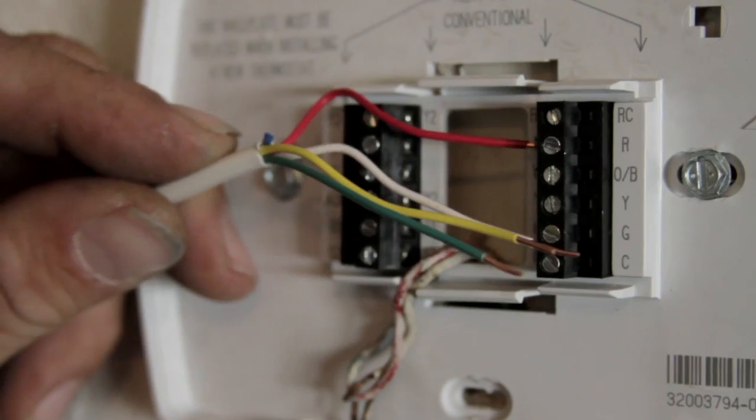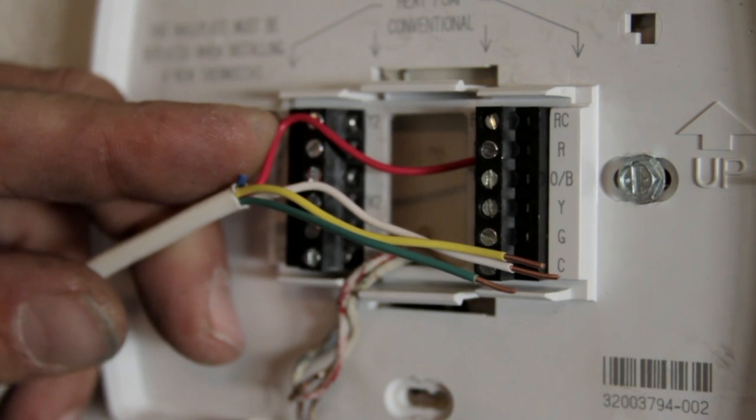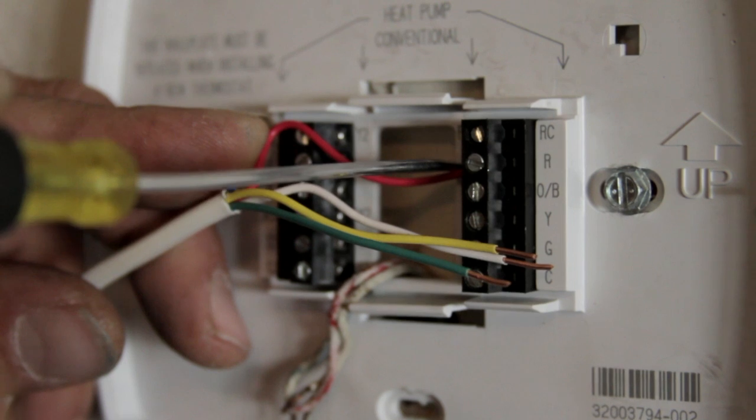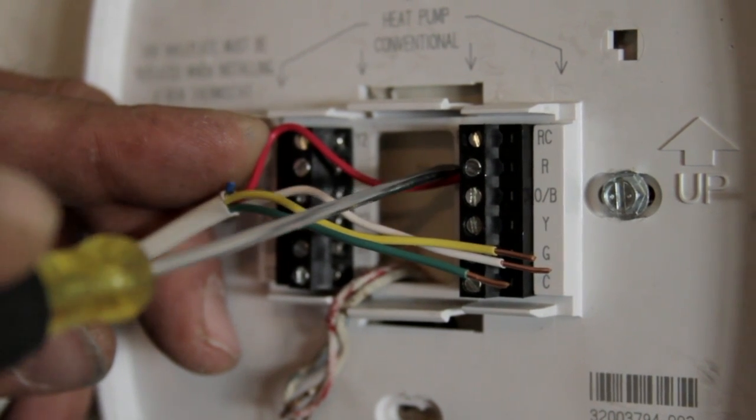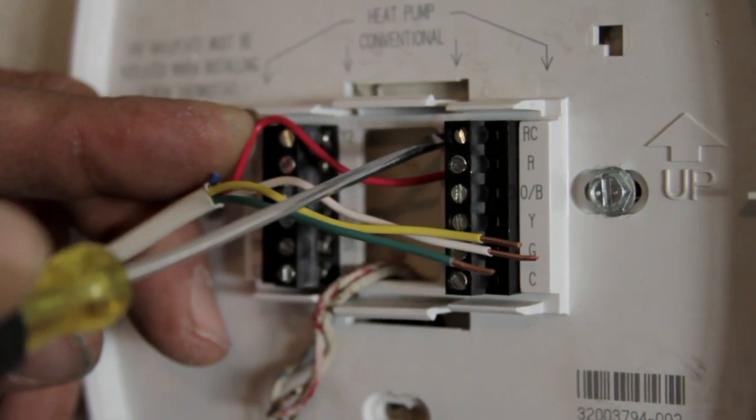With wiring a thermostat, what you're going to want to do is push the wires in. The biggest thing to remember is that on this thermostat there's an R and an RC. Now R represents 24-volt heating and RC represents 24-volt cooling.